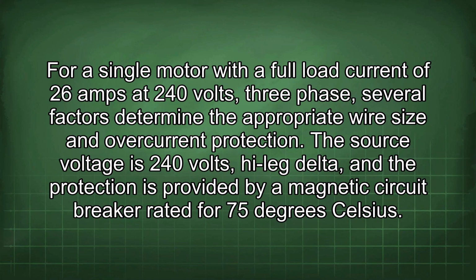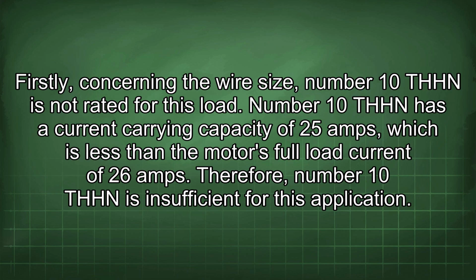For a single motor with a full load current of 26 amps at 240 volts, three-phase, several factors determine the appropriate wire size and overcurrent protection. The source voltage is 240 volts high leg delta, and the protection is provided by a magnetic circuit breaker rated for 75 degrees Celsius. Firstly, concerning the wire size, number 10 THHN is not rated for this load.